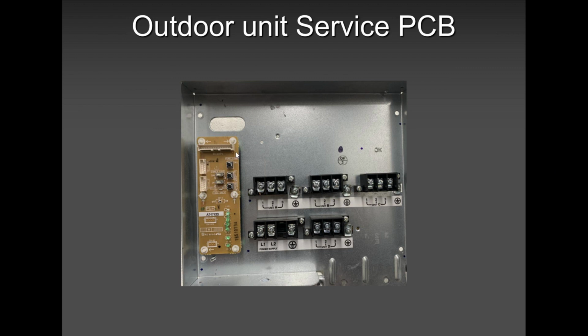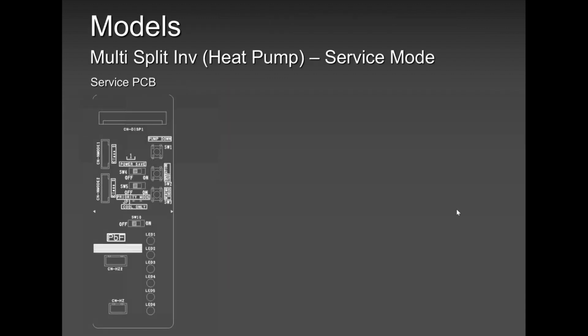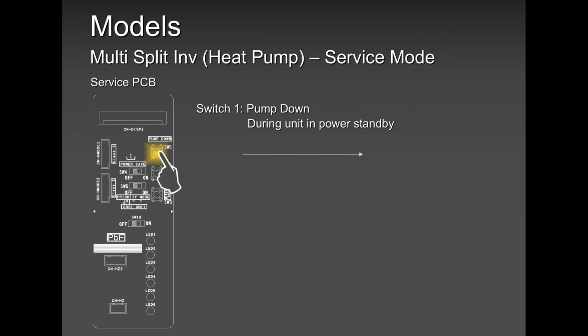Now let's talk about this service PCB. On a multi-zone, you will see this PCB on the left-hand side when you open up the panel where you have all these wires here. Your main power comes here, your unit A, B, C, D, okay? So that service PCB talks about many things, but I want you to focus on a few things only. A few things like pump down. You have the pump down option. You can pump down the system, no problem.